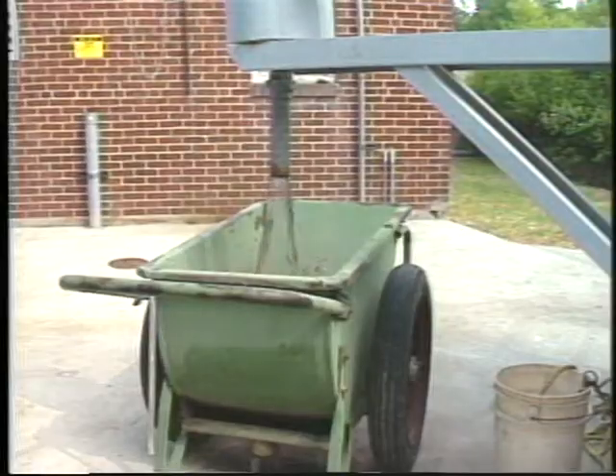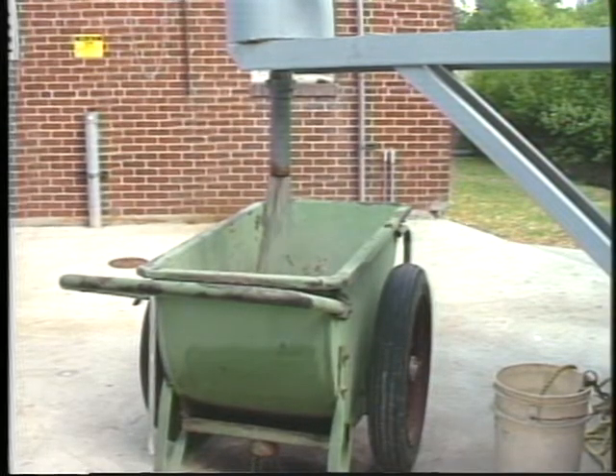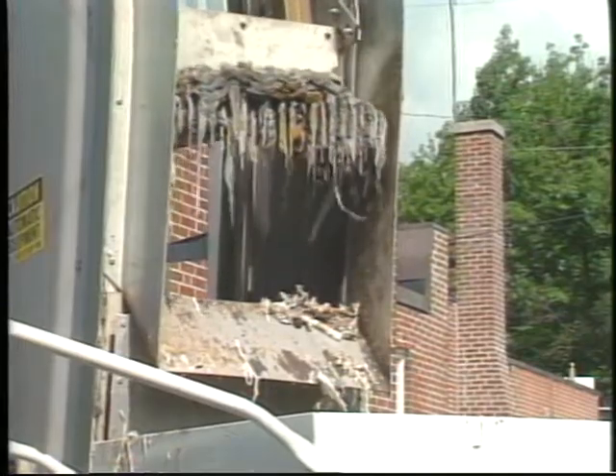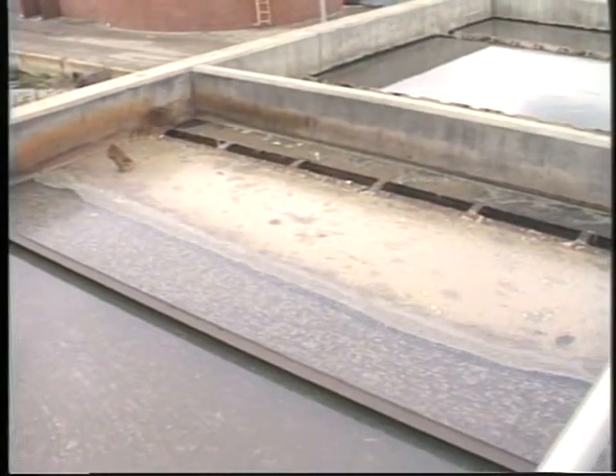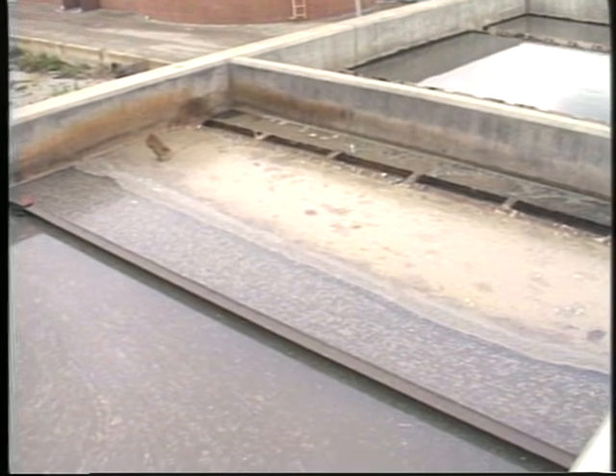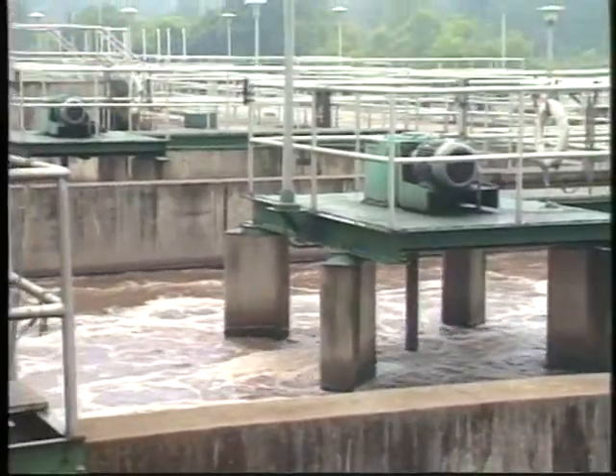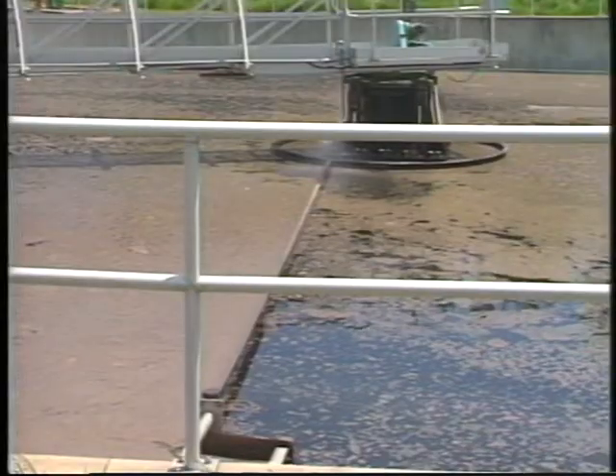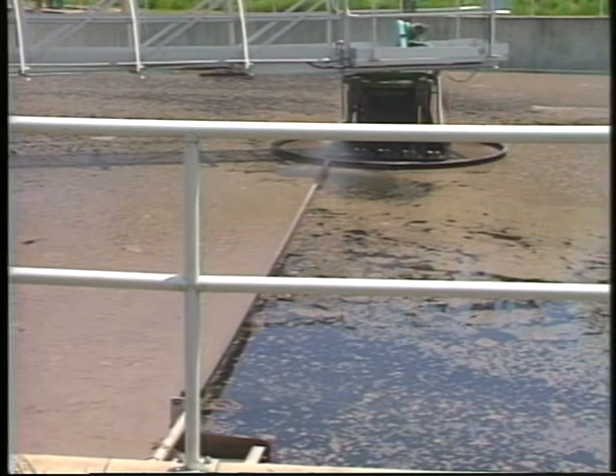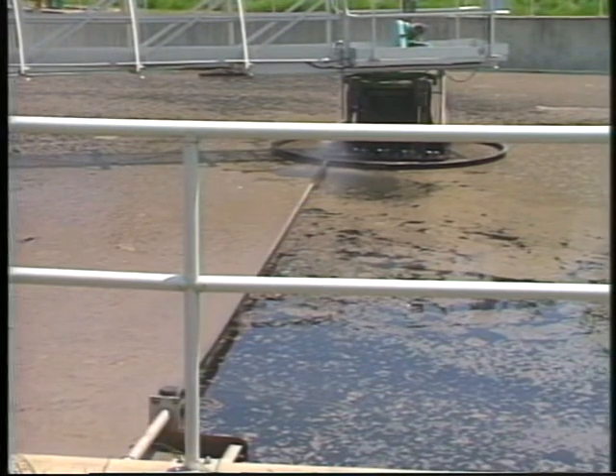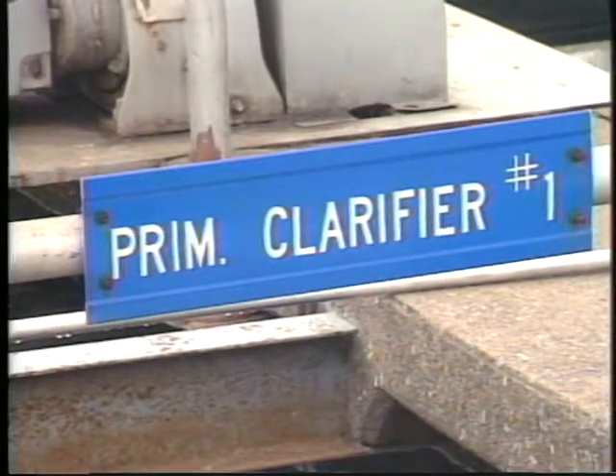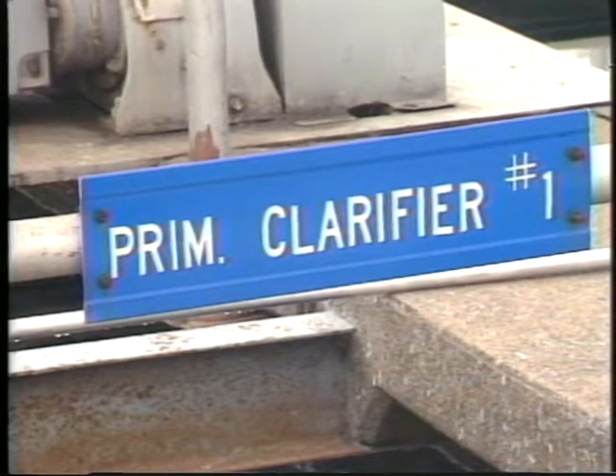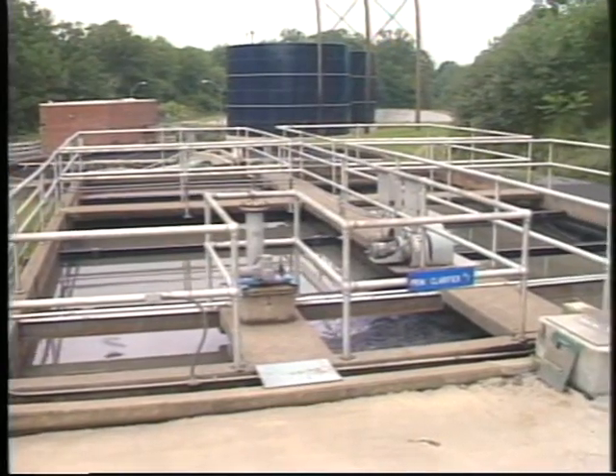Now, after wastewater has passed through the preliminary treatment stage, grit and screenings have been removed. However, the wastewater still contains copious amounts of solids that also need to be removed and treated. In addition to wastewater passing from the preliminary treatment stage, wastewater that is flowing from a biological treatment unit will contain solids that need to be removed as well. The process of removing settleable and floatable solids from the wastewater is usually accomplished with a treatment unit known as a clarifier, which facilitates a process called sedimentation and flotation.